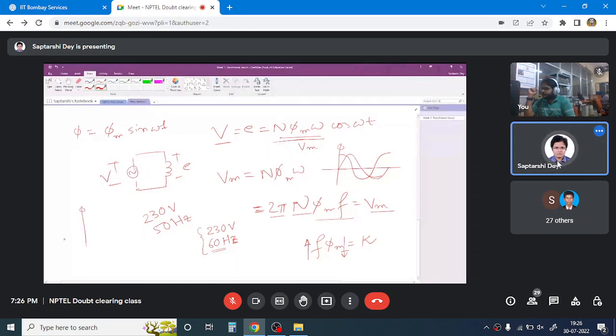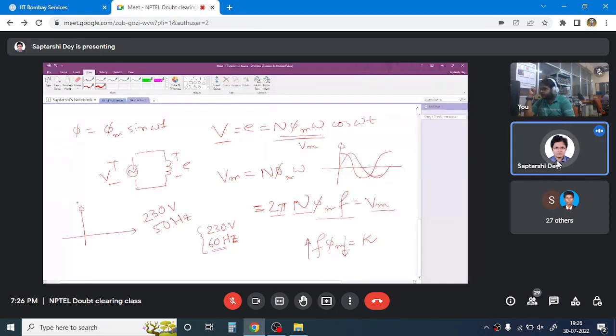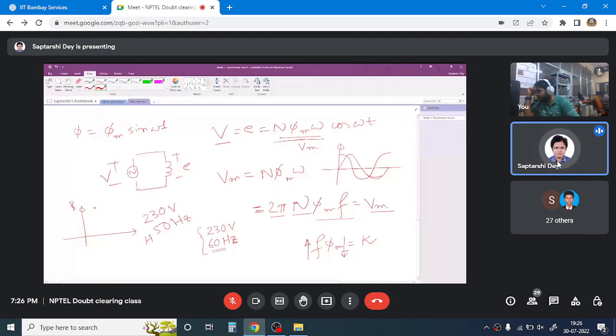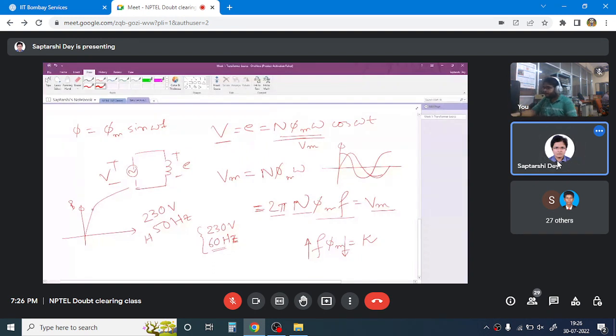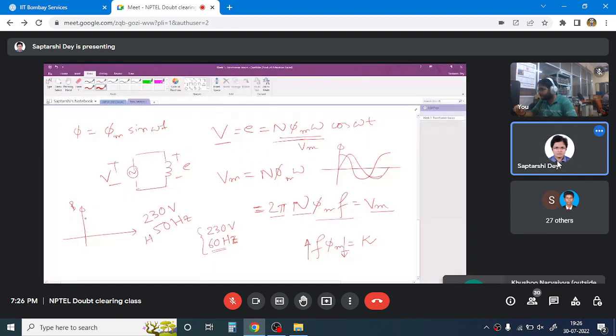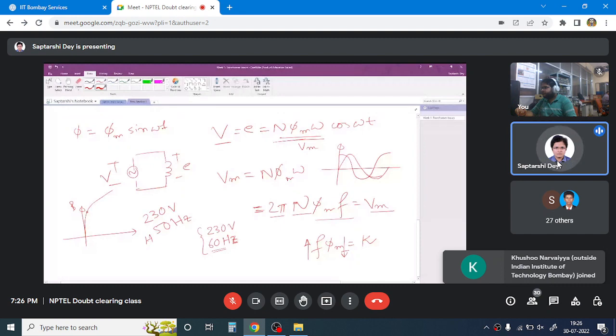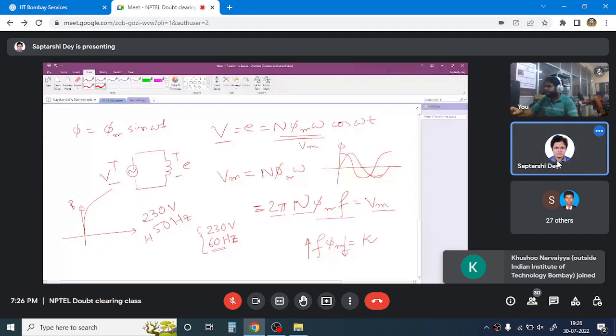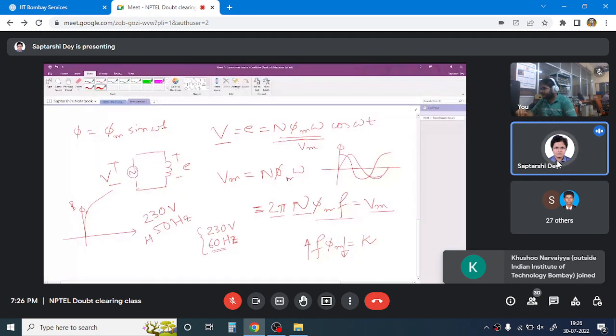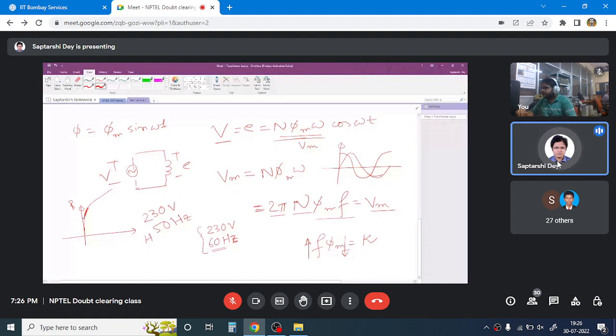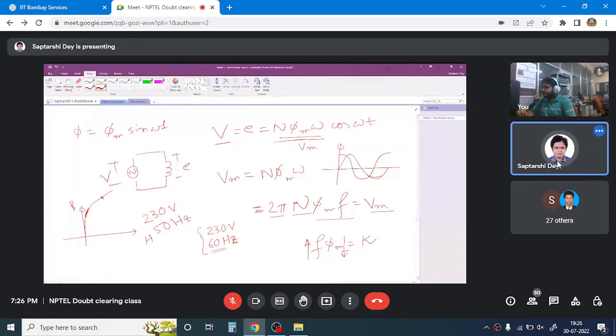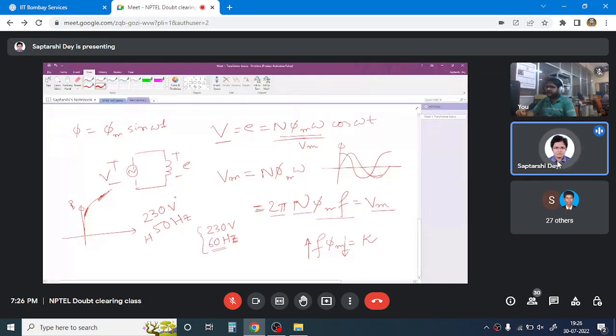When we are designing the core, this is the BH curve of the material we use, and we make sure the perturbation stays in a certain zone where the flux varies. Now if you connect it to a very low frequency, your B will increase, and you will operate beyond that zone. As a result, your magnetizing reactance will drop at that condition. This is called saturation.